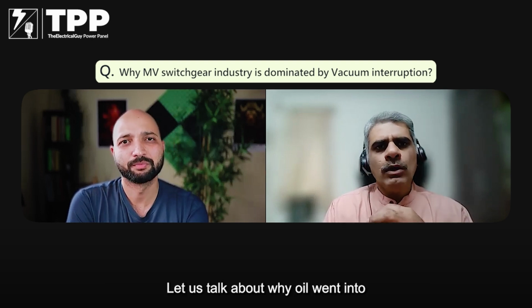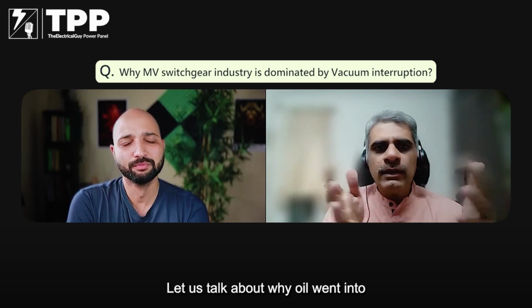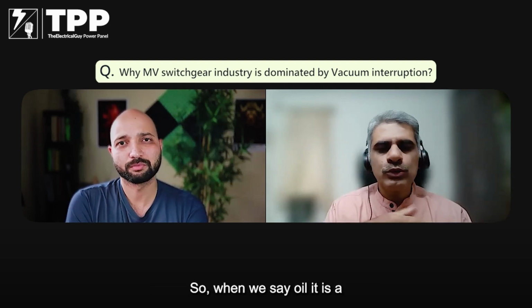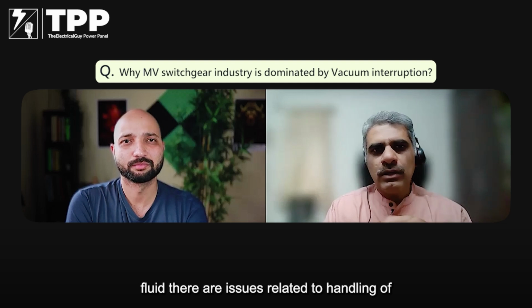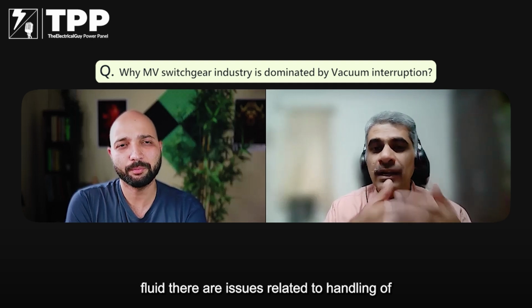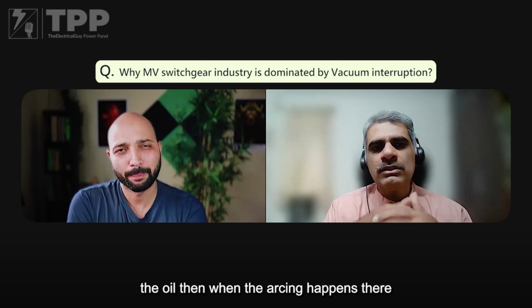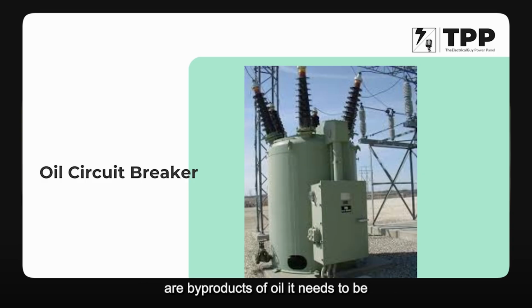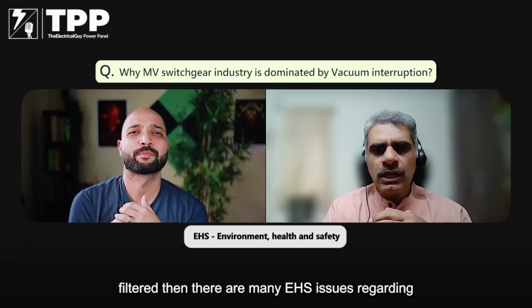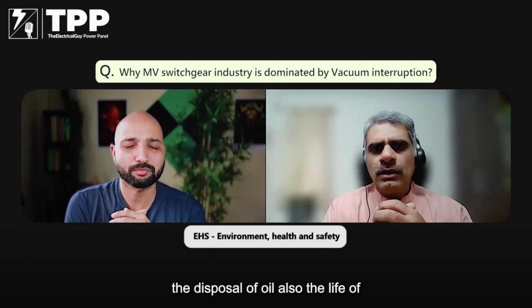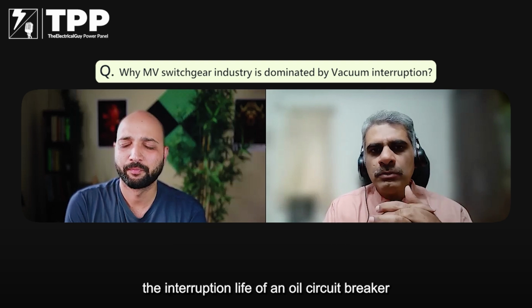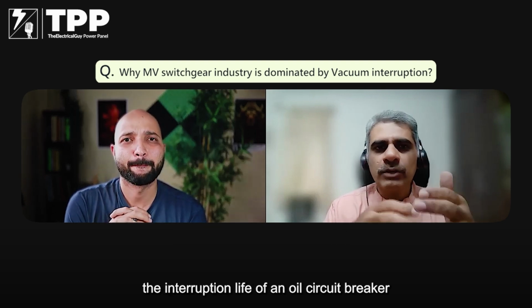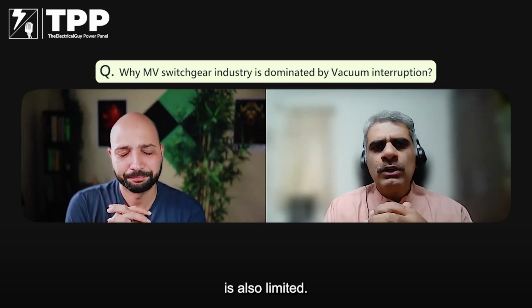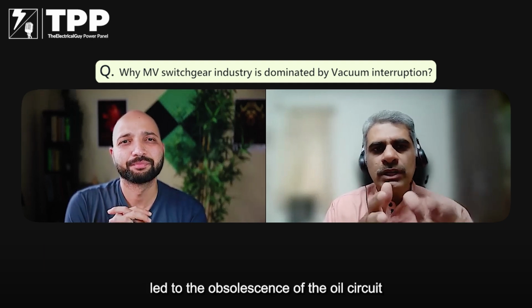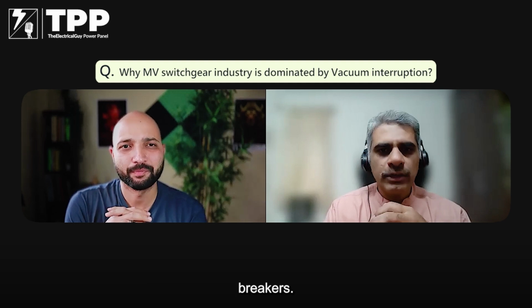Let's talk about why oil went into obsolescence as compared to vacuum. When we say oil, it's a fluid. There are issues related to handling of the oil. Then when arcing happens, there are byproducts of the oil, and it needs to be filtered. Then there are many EHS issues regarding the disposal of oil. Also, the interruption life of an oil circuit breaker is limited. So there were a number of factors which led to the obsolescence of oil circuit breakers.